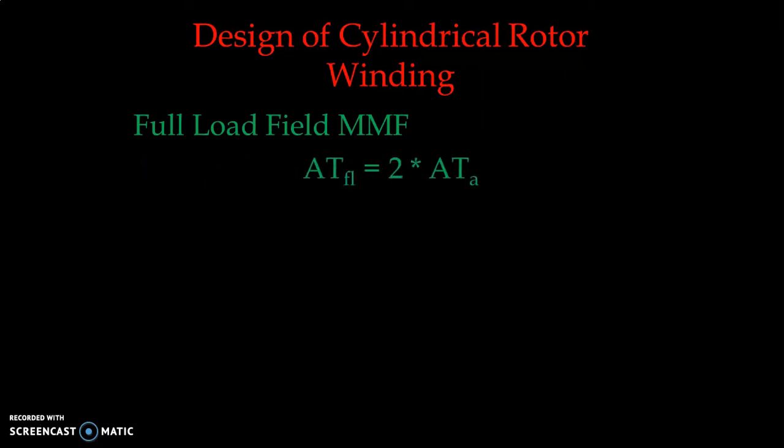We start with the full load field magnetomotive force. The first step in the rotor winding design is to find how much MMF this winding will generate. Based on the required flux and flux density, we design our ampere-turns, and from those we find the number of turns and field current. The full load field MMF — ATfl — is normally taken as two times the armature ampere-turns.